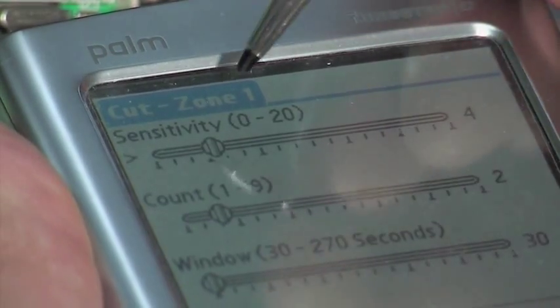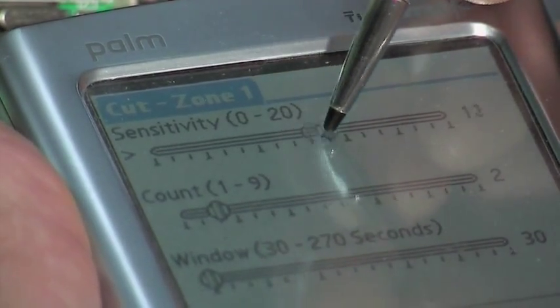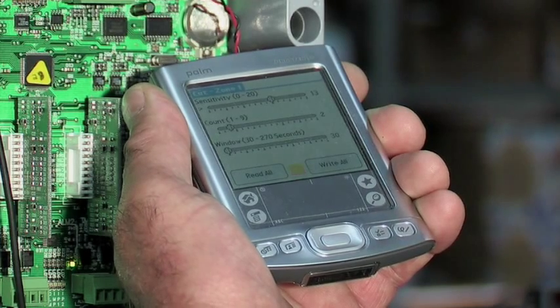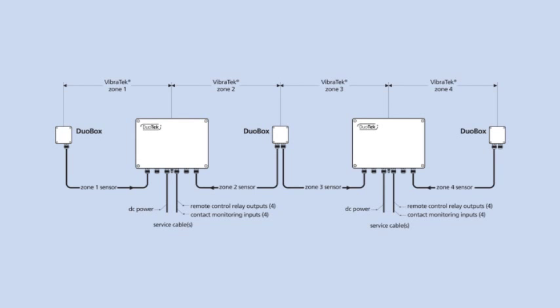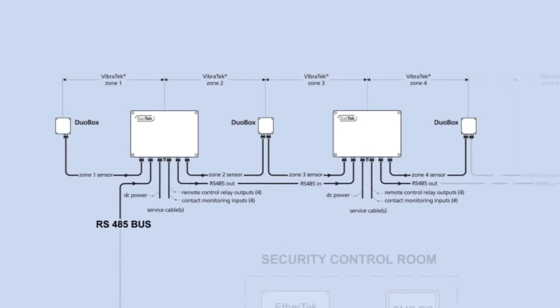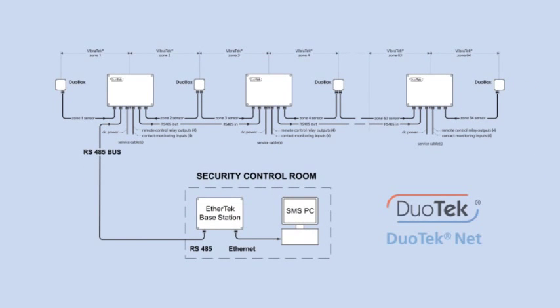Convenient adjustment of settings is achieved via an infrared port and a handheld PDA. For larger applications, multiple DuoTek signal analyzers can be linked together via a rugged RS-485 communications bus to form a distributed network in which each analyzer can be up to 600 meters from its nearest neighbor.